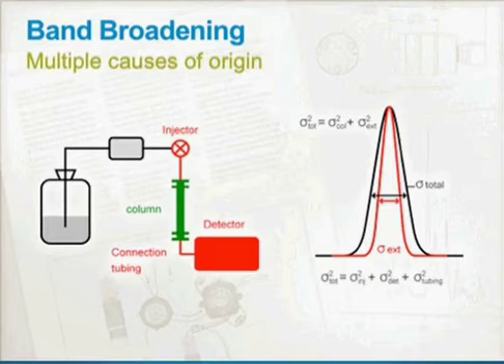Yeah, and we might want to explore that topic just for a second, too. Common convention, when you take LC in school, they talk about not doing anything to the fluid downstream of the column. So a perfect system would have column separation going straight to the detector or the electrospray, whatever you're going to use. But what you've done is you've added all kinds of things in there, and you're saying you still didn't get peak degradation, or you got a minimal amount? A minimal amount. I mean, no one ever wants to claim that by putting things on a flow path you're not doing something to the system. But what you really want to avoid is asymmetric peak broadening and excessive peak broadening. And if you can achieve that and yet at the same time improve your detection efficiency for the analytes of interest, you've actually won, and that's what we've achieved.